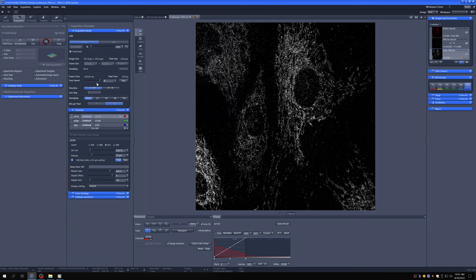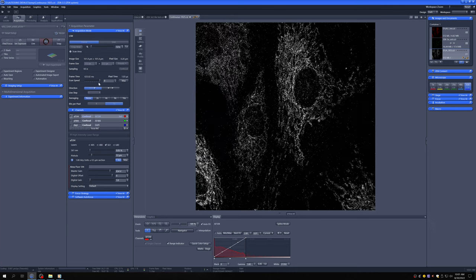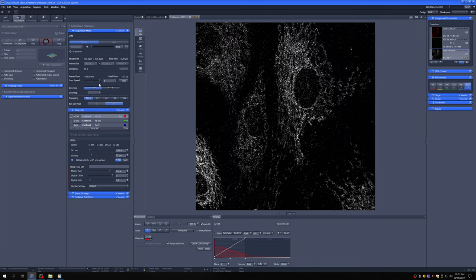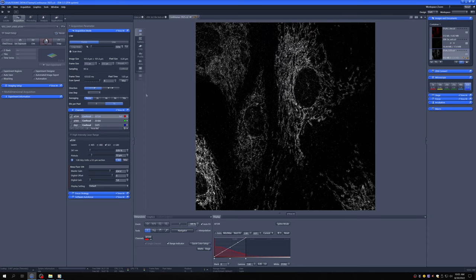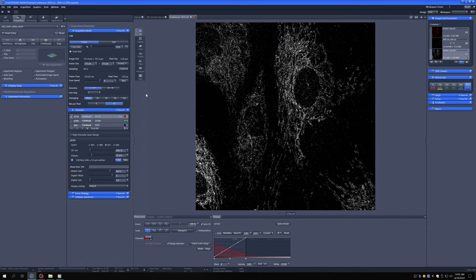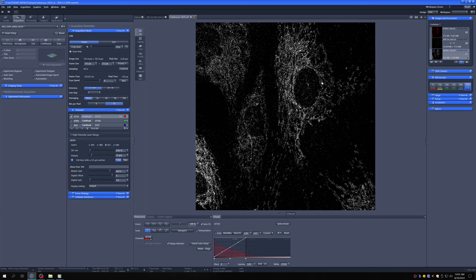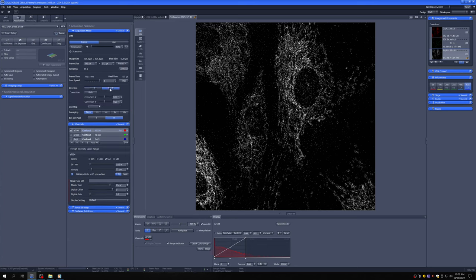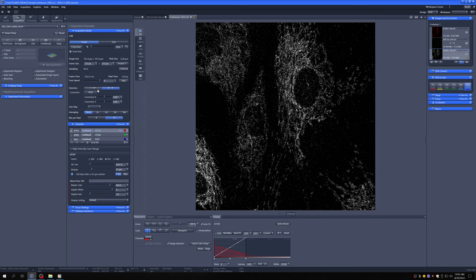There's another condition under which lowering the scan speed can have benefits, which I'll discuss now in the context of bi-directional scanning. As I've mentioned, this is a laser scanning confocal microscope, meaning that the laser moves in a raster pattern through the sample. The details of that raster pattern are defined here in this direction button. Direction with this arrow or unidirectional means that the laser moves from left to right one line, then the laser turns off, flies back, moves down one line, turns back on, and moves from left to right again. This is sort of like a typewriter pattern. If you click on this, the laser swings back and forth in a snake pattern. Obviously this is faster because as the laser goes back in this mode it's imaging, whereas it flies back in this mode. And you can see that reflected in the frame time.